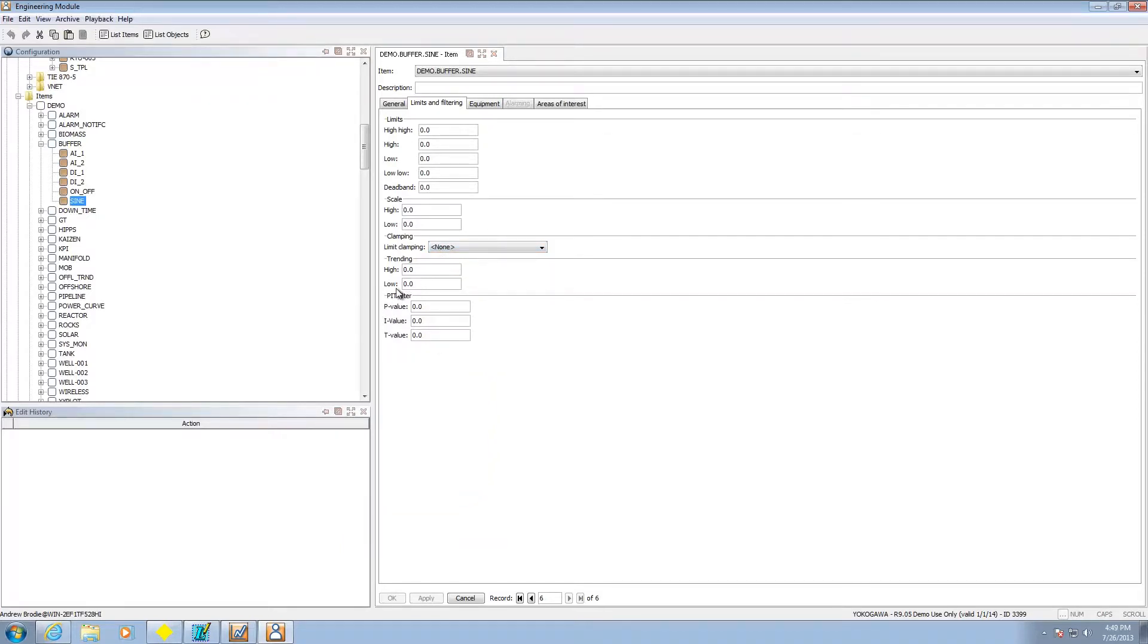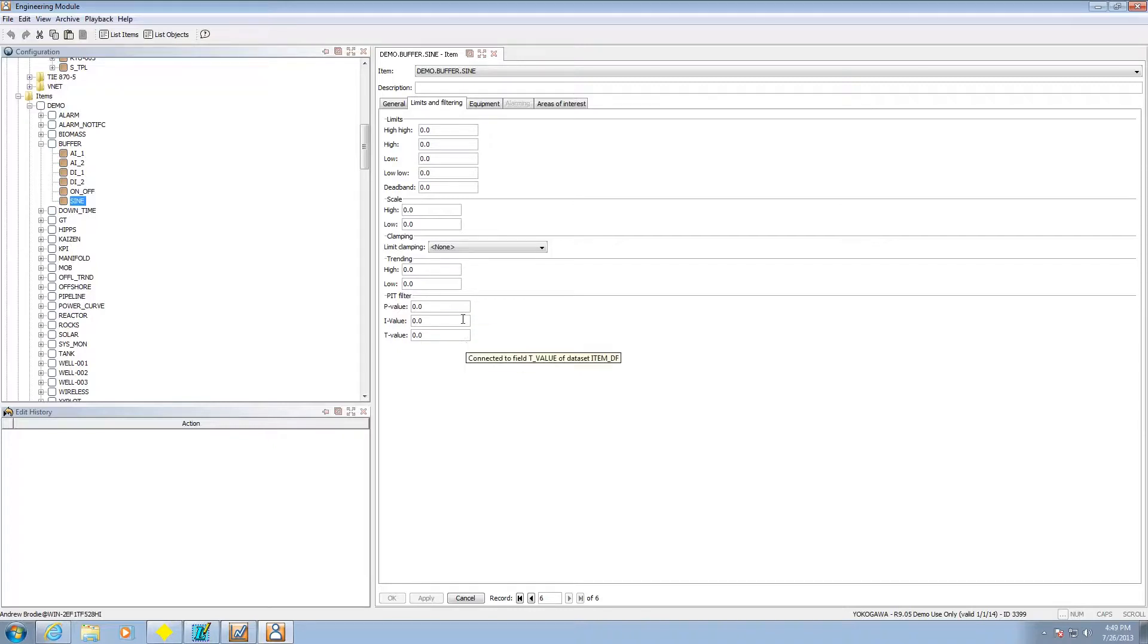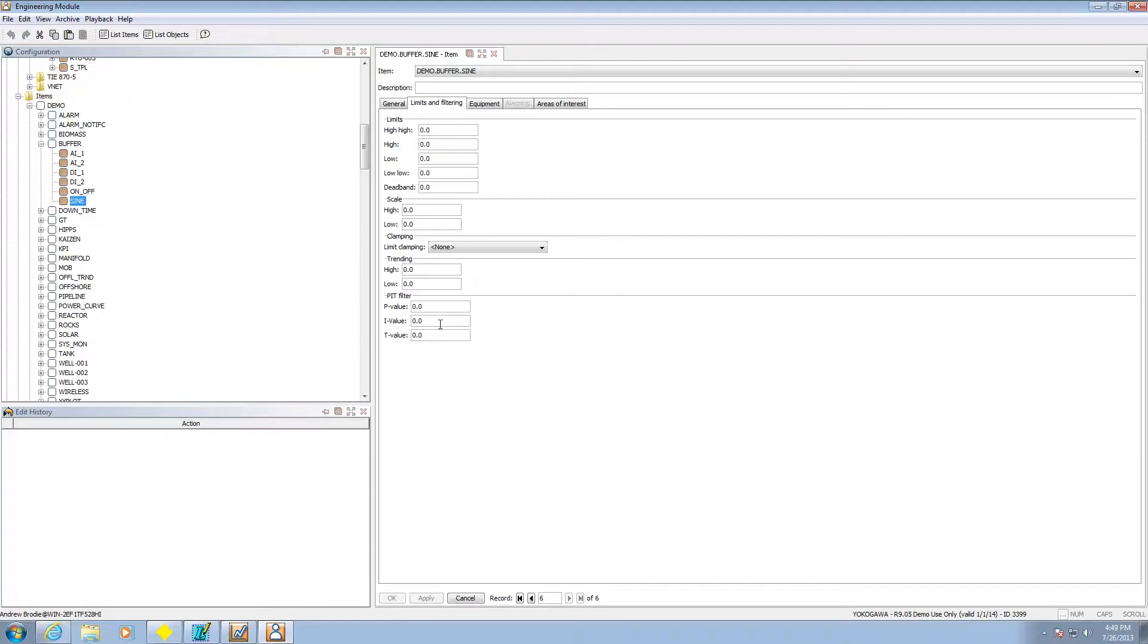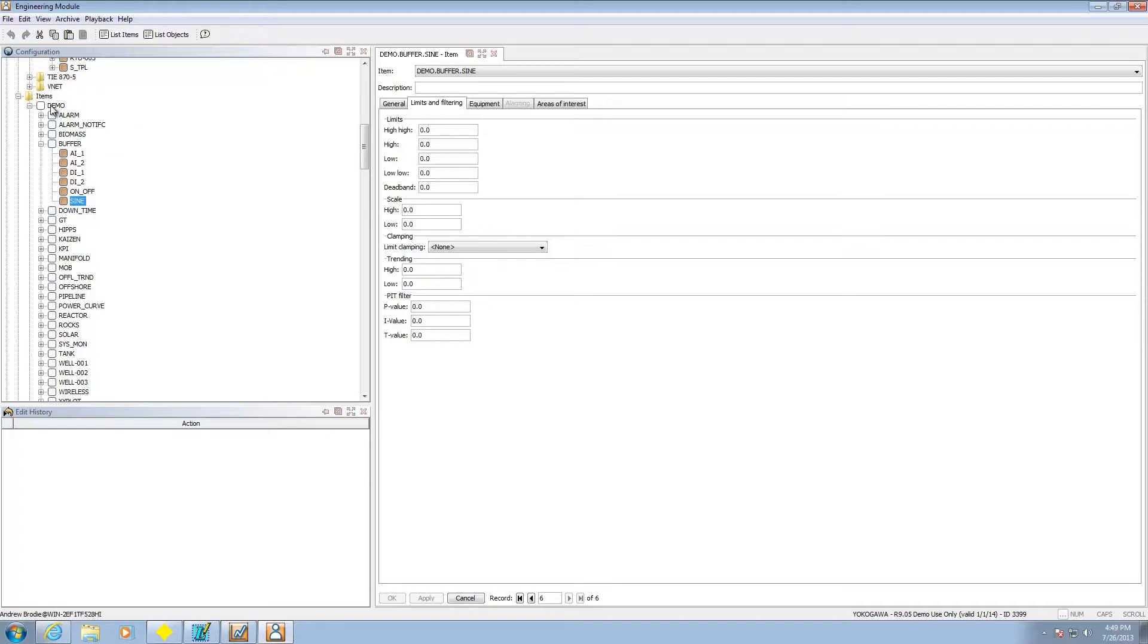One of the things I'm going to show when I show you how to set up the historical data logging is you can say pass the PIT filter. So this PIT filter can show you some conditions about when it's actually worth doing a historical data logging. For example changed a certain amount in a certain amount of time that would be set up through the PIT filter.